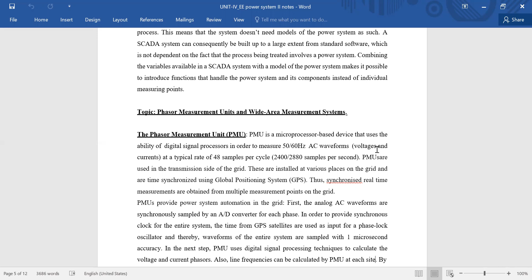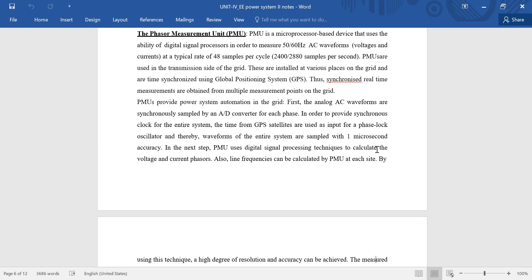Then the next step: the phasor measurement unit uses signal processing techniques to calculate the voltage and current phasors. Also, line frequencies can be calculated by the PMU for each phase. We use this technique to achieve a high degree of resolution and accuracy. The measured phasors are tagged with GPS time stamps, and then transmitted to the PDC, that is the phasor data concentrator, at the rate of 30 to 60 samples per second, right?